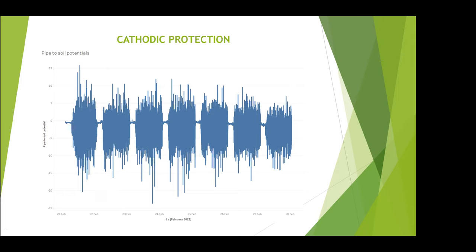When we write the standards for cathodic protection, we tell people what potentials to achieve. Taking approximate figures, we would take minus one as about the kind of potential you expect to see. So you can imagine if you're expecting minus one and you get minus 20, there's a great deal of panic — because if you take a pipeline too negative, you can start to evolve hydrogen from it and change its mechanical properties. These extreme potentials have been the cause of a great deal of concern over the years, and a lot of it has been unnecessary, fueled by people who don't really know what they're talking about, frightening clients — because we have to look at an averaging, not just an instantaneous potential.